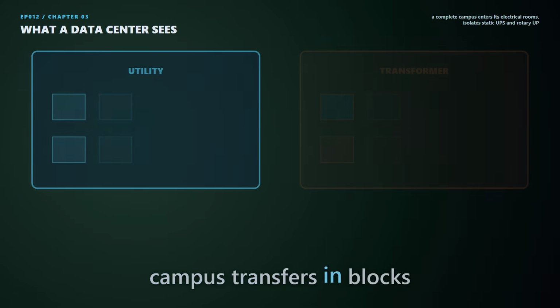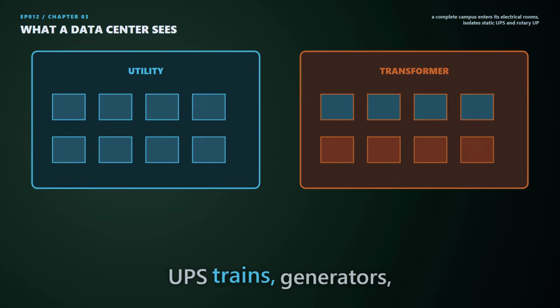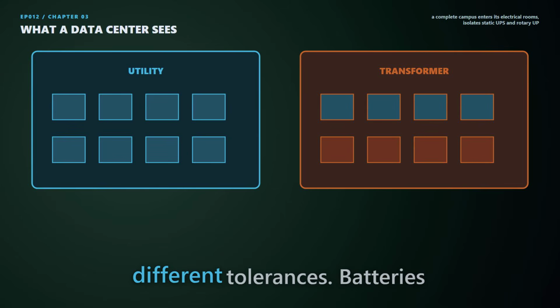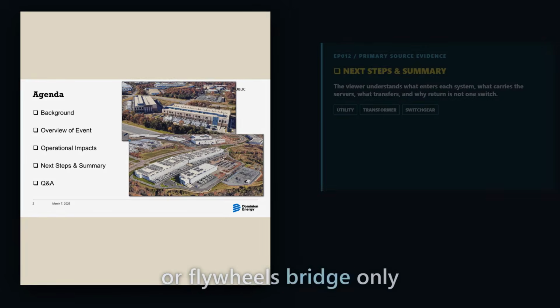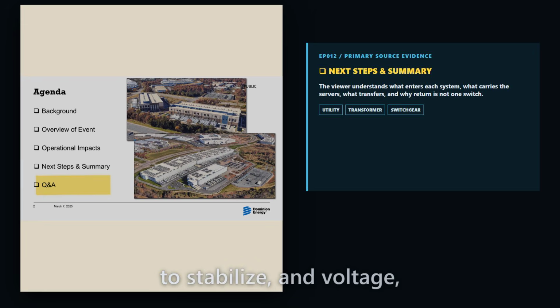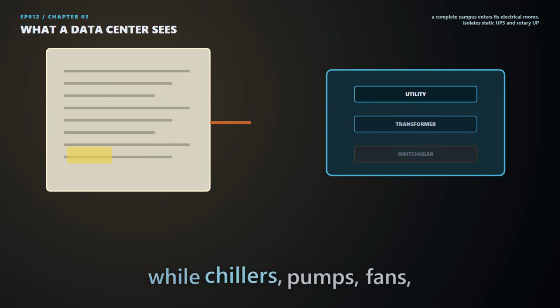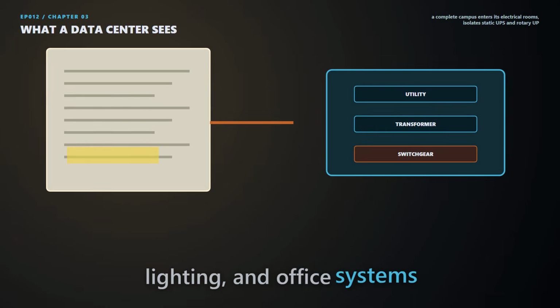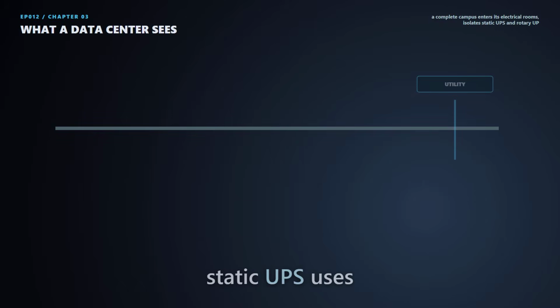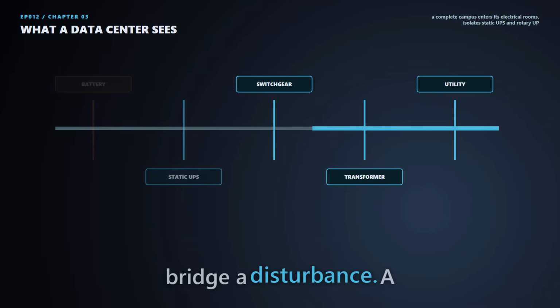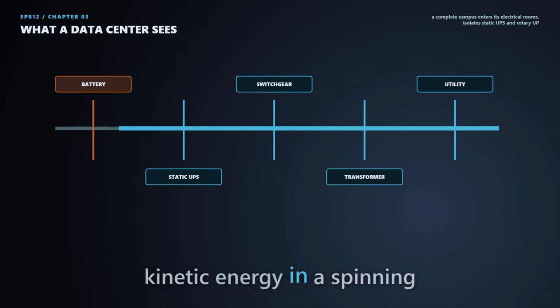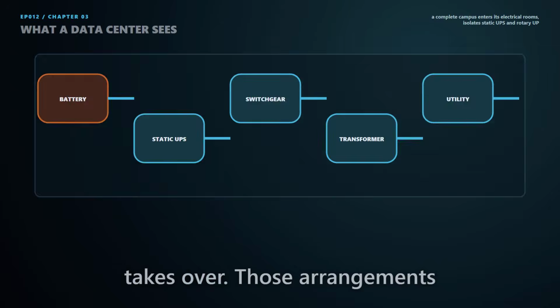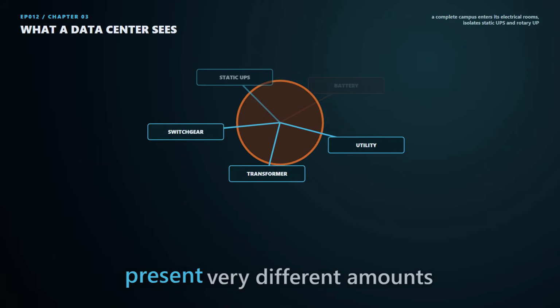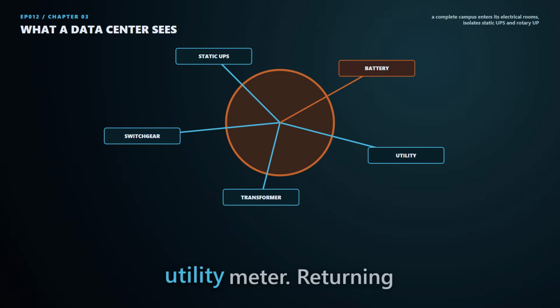A campus transfers in blocks across electrical rooms, UPS trains, generators, and mechanical systems with different tolerances. Batteries or flywheels bridge only long enough for the next source to stabilize, and voltage, frequency, and phase must remain within limits during the handoff. Critical computing load may remain behind power electronics, while chillers, pumps, fans, lighting, and office systems follow other paths. A static UPS uses batteries and electronics to bridge a disturbance. A rotary design stores kinetic energy in a spinning machine until an engine takes over. Those arrangements can preserve the servers yet present very different amounts and timing of load at the utility meter.